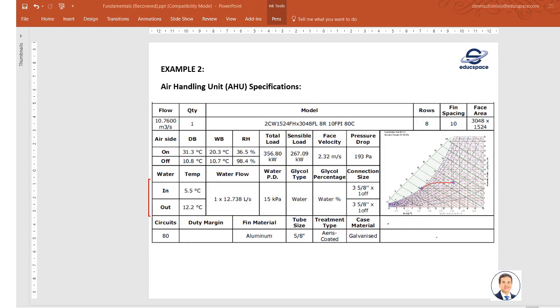Now let's try to verify the values using the concept we studied. Consider that you have an air handling unit, and you want to verify the data given to you by the supplier or distributor. You can verify if the capacities match what they put in the specification. Here is the typical data: number of rows of copper tubes, fin spacing like 10 fins per inch, face area, model, quantity, flow rate, airside values. Dry bulb on-coil value is 31.3, wet bulb is 20.3, relative humidity is 36, and the off-coil condition is 10.8. Let's verify if what they put is correct, because sometimes there's cheating.